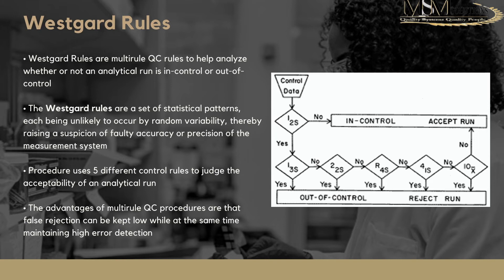If there are not two such values, you then check the R4s rule. This means comparing the current value with the previous one: if the previous value was at minus 2s and the current is at plus 2s, the two values are four standard deviations apart. If that condition is met, you also reject the run.